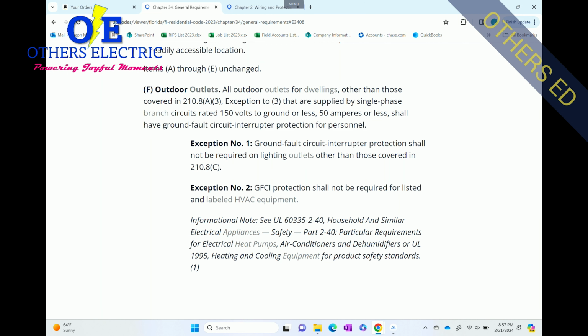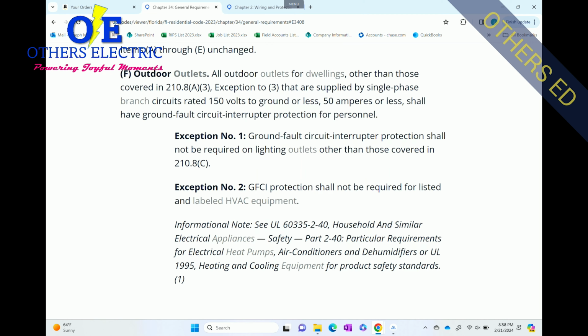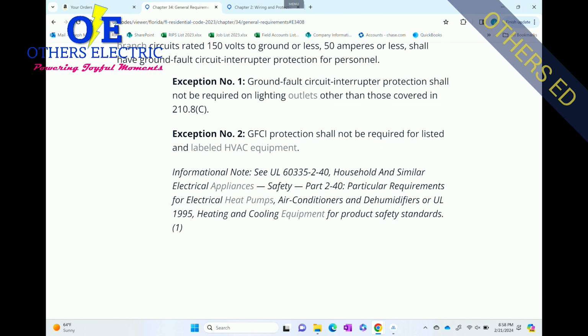F, outdoor outlets. All outdoor outlets for dwellings, other than those covered in 210.8(A)(3) exception to 3, that are supplied by a single-phase branch circuit rated 150 volts to ground or less, 50 amperes or less, shall have ground fault circuit interrupter protection for personnel. That's changed. There's an exception. Number 1, ground fault circuit interrupter protection shall not be required on lighting outlets other than those covered in 210.8(C). That's unchanged. But look here, exception number 2. The Residential Building Code in Florida, 8th edition, added this amendment: GFCI protection shall not be required for listed and labeled HVAC equipment.